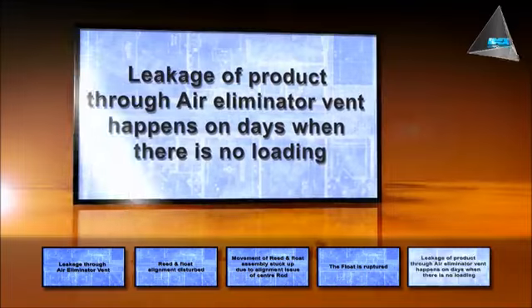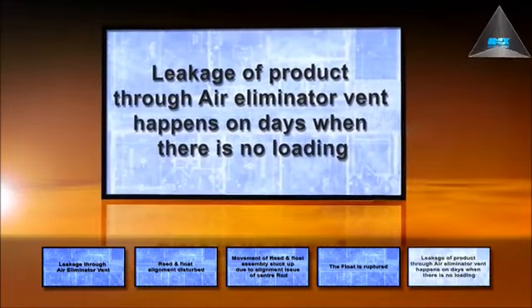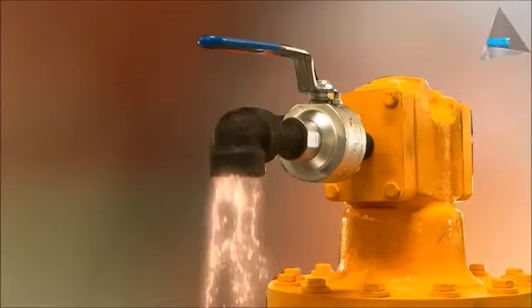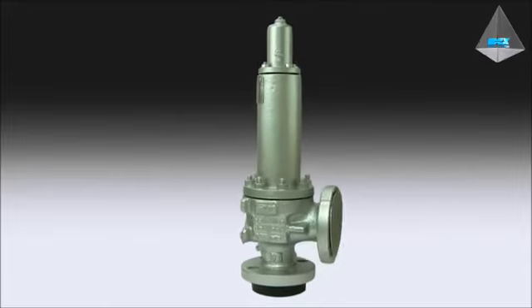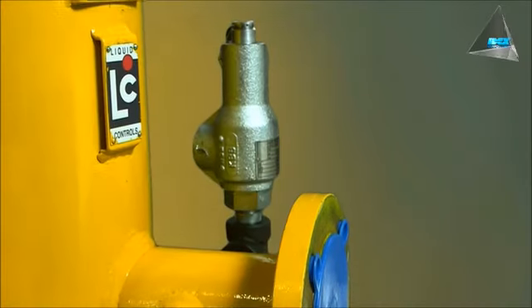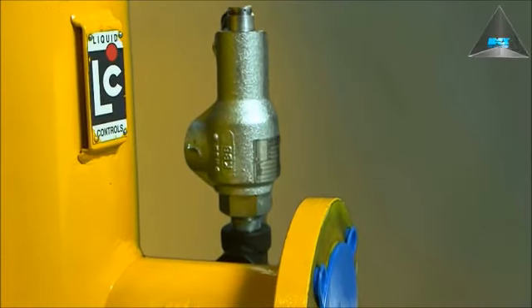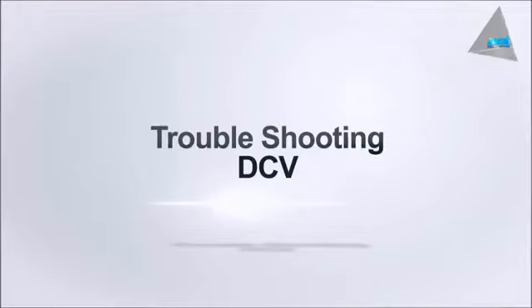Leakage of the product through the air eliminator vent happens on days when there is no loading. Solution: ensure that the thermal relief valve is installed on the air eliminator flanged elbow to account for thermal expansion of the product. Troubleshooting: DCV.